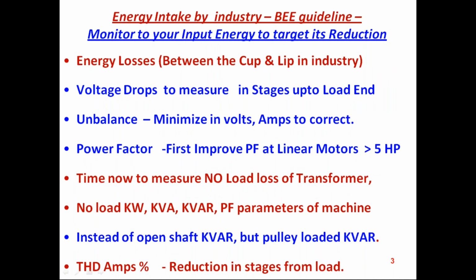We are concentrating more on the energy flow in the industry. We call it a Sankey diagram, and we are concentrating more on the energy flow to the industry. The energy intake by the industry, the Bureau of Energy has given the guidelines. But if we see the energy flow in the industry, we can see what is the cup to lip loss in the industry, especially the voltage drops on the electrical network. And if it is a three-phase load, the voltage unbalance or the current unbalance is causing problems with all the loads, the three-phase motor loads.